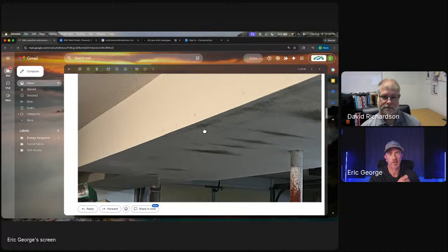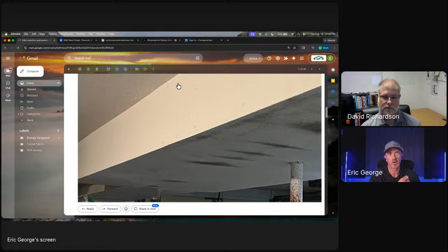The other challenge might be, depending on whether the ductwork goes all the way up to the floor joist here, getting insulation all the way around the ductwork might be tough. But one way or another, everywhere there's a strap connecting two pieces of this trunk line together, that connection needs to be sealed with metal tape or duct mastic.